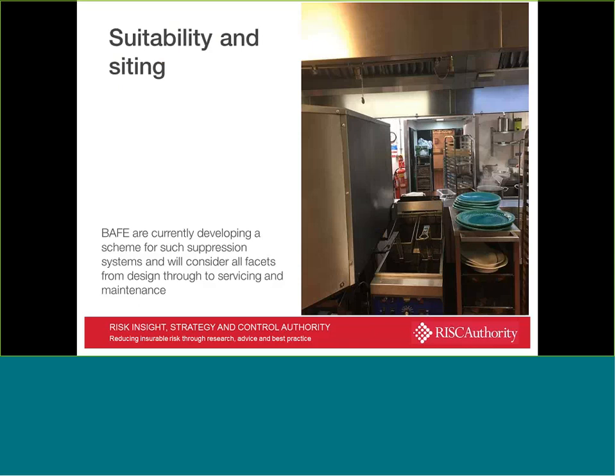There are also issues in terms of the suitability of the system and the siting of the system. It's just an example there of a kitchen that I was looking at recently with a deep fat fryer that is cunningly placed perfectly between two nozzles. No guarantee whether either of them will actually do the job in terms of suppressing a fire that may have occurred in the deep fat fryer. But sadly, with some of these systems, particularly electrical powered devices or others that aren't necessarily tethered, they can be moved around the kitchen, and that doesn't always mean that the suppression system will remain valid for the layout that remains.